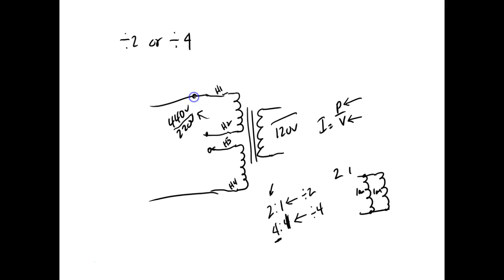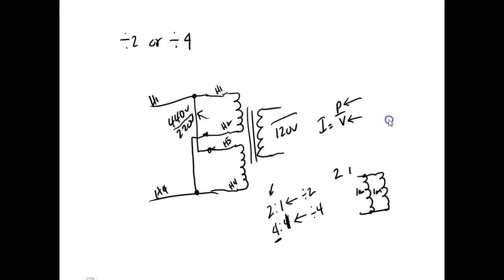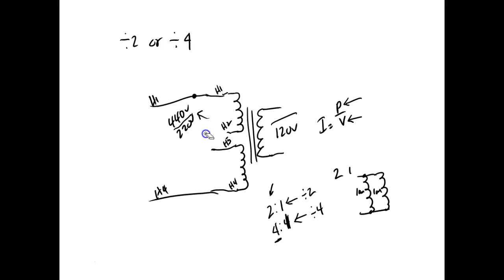Now look, all these wires up here cross. What they decided to do on the transformer - did you see how it was numbered? It goes 1, 3, 2, 4. That's right, and this is what I tried to show y'all the other day. So if they come over here and cross this, it makes it real easy to see if it's wired right or wrong. What they do on the transformer is bring up and cross these 2 right here. They're not crossed in the wiring of the transformer - they're crossed when they bring the H1 and H2 leads out of the transformer. So they come up here and cross them like that.